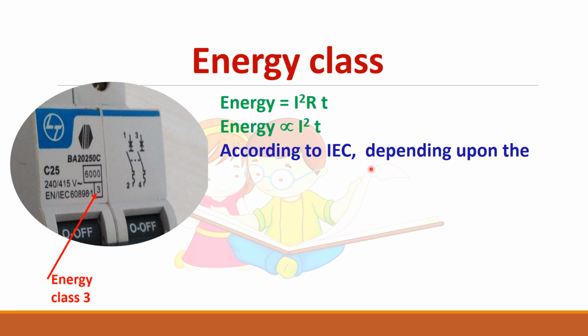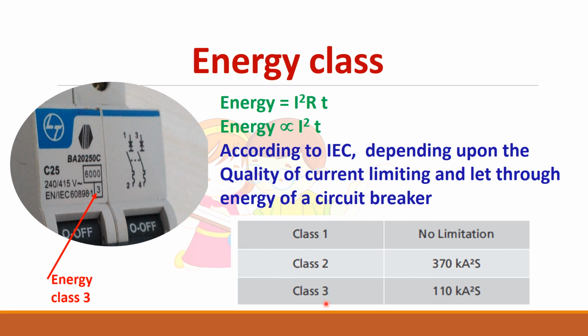According to IEC, there are 3 classes, out of which most of the breakers are of class 3, which will allow only very little energy to flow through the breaker during the faulty condition. So class 3 is said to be the best class for the breaker. So always prefer this type 3 MCB for your home.